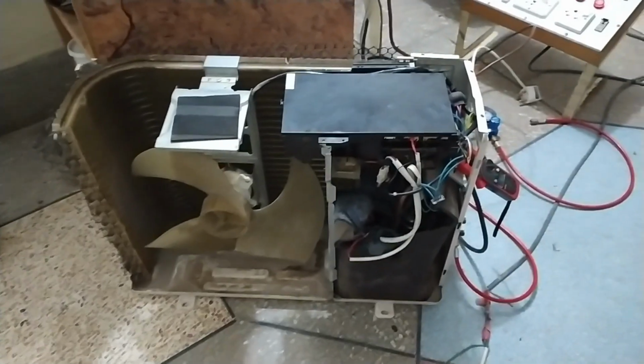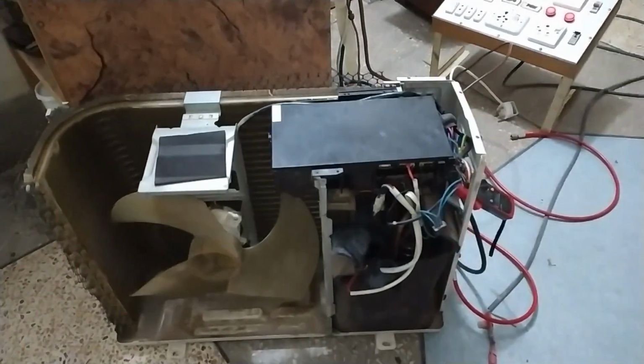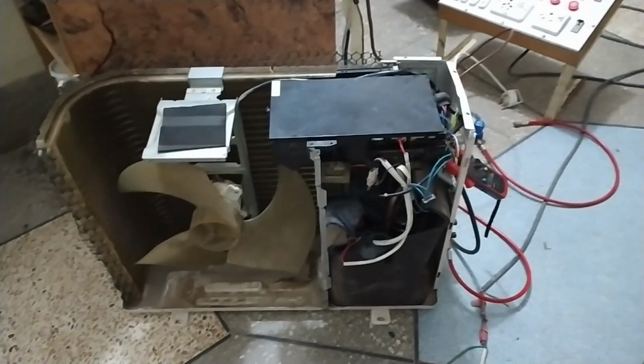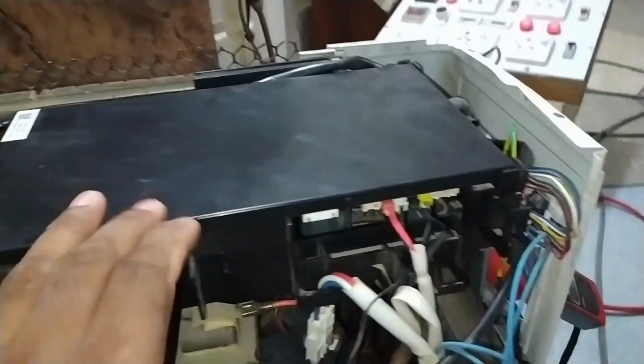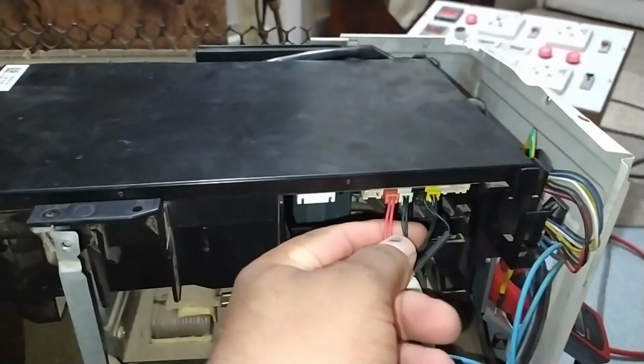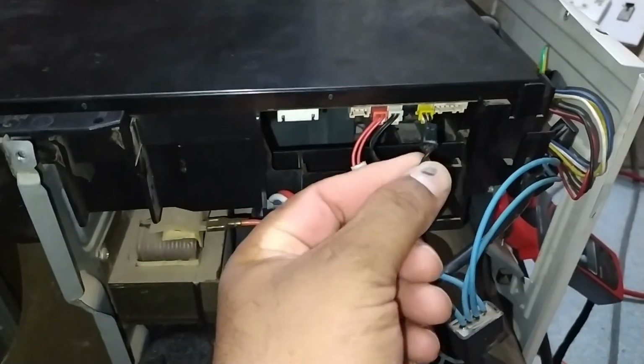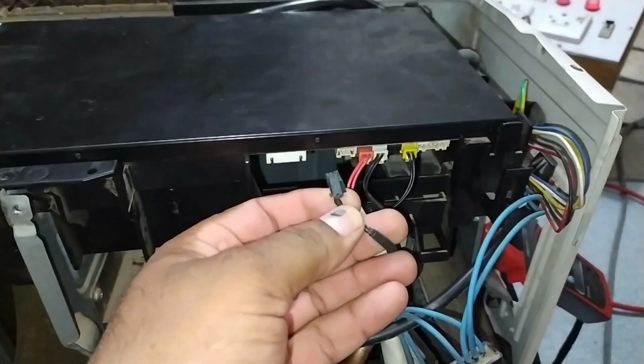Another error code is showing on the display. The set temperature is 16 and the error code is 1. Since this is also an outdoor unit fault, let's check what the issue is in the outdoor unit. Now we have moved to the outdoor unit, and I will explain in complete detail why error code 1 appears. Look at this PCB. You can see that it has 4 sensors. Whenever the sensor connected to the black connector becomes faulty, it causes error 1.